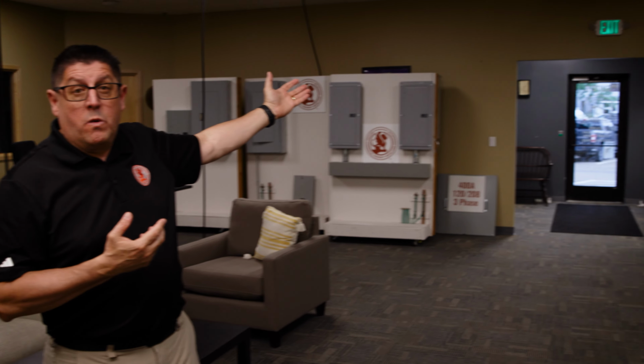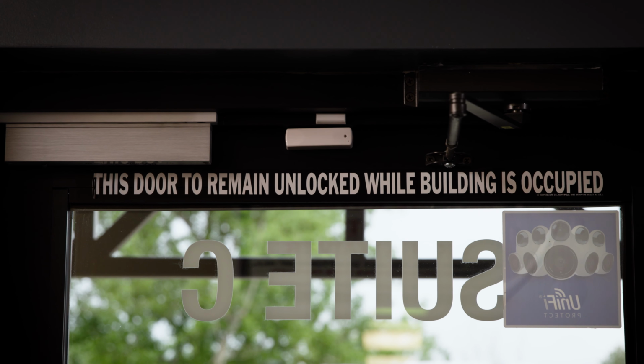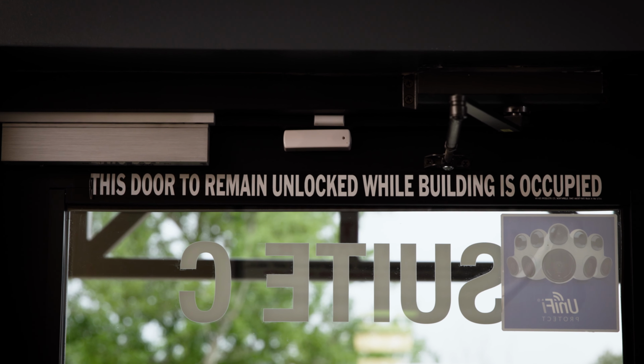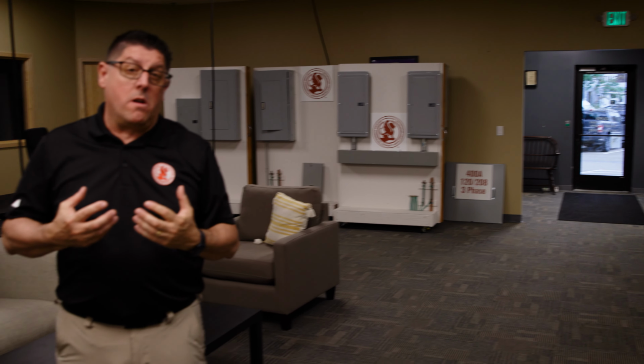When inspecting the interior and looking at the exits, we need to put ourselves in the mindset of somebody trying to leave in the event of an emergency. We came in at the front door, which is clearly delineated as an exit. We have a nice sign above that door. And then remember, if the building is less than 75 foot deep, we only need one exit out of the building.